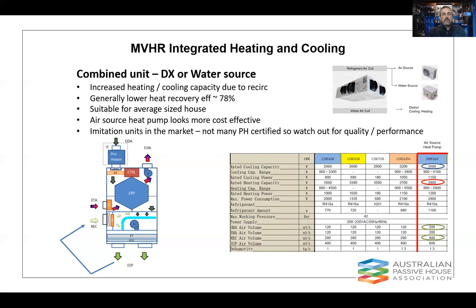Now, what has been stumbled upon or evolved is the idea of having a recirculation loop. If we look down in the bottom left-hand corner, you can see where I've drawn the blue line. So as well as air coming in the outdoor or ODA port on that unit and through the unit, we're also supplying some air that's been heated or cooled into a living area, and that has a recirculation loop. So now the airflow across the heating cooling coils can be roughly double what it was, because it's no longer just related to the exact HRV airflow capacity. So hopefully that makes some sense, and we can now get more like 4 kilowatts up in that sort of area, heating and cooling, which starts to make the application a little bit broader.